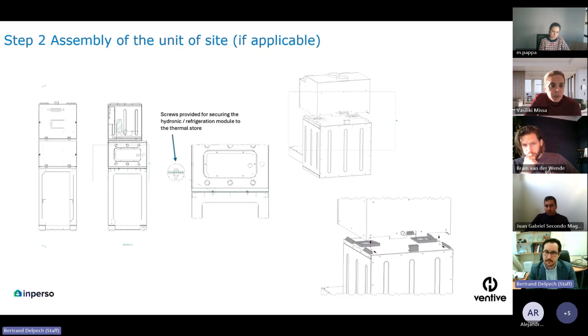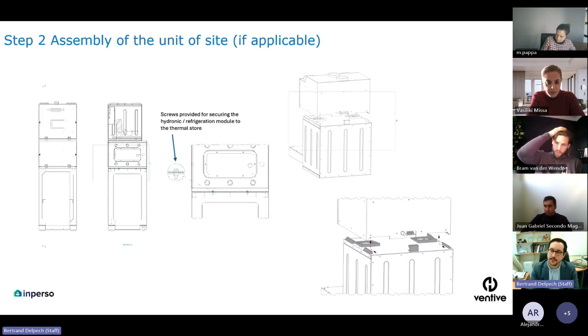You just need to bolt it in place and then do the water connection and electrical connection, for which we will give guidance if it is required in this project, or we will do it because we'll also be on site with the demonstrator. And then finally, the last part is the AHU unit, which just slides on top, and there is nothing else to do except connecting the power supply for the fan and the sensor connection. So this is in the case of a disassembled unit that needs to be reassembled.